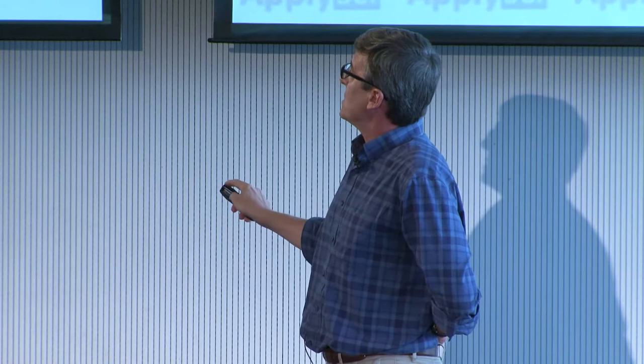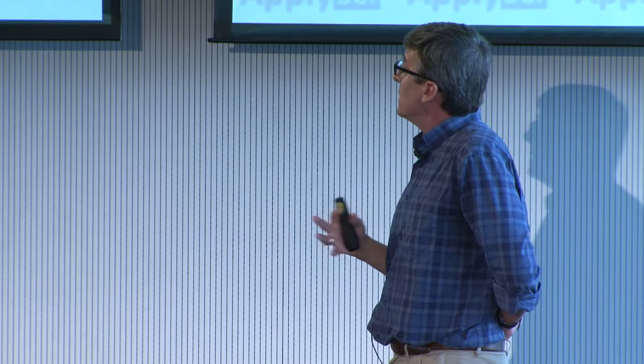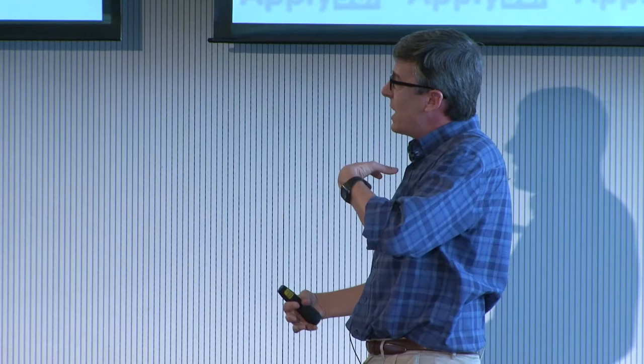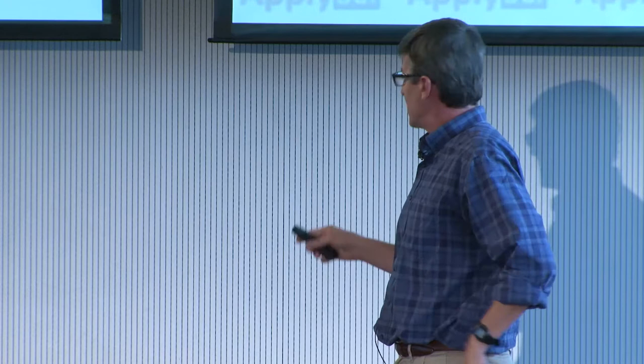So it has a pair of LEDs, one red, one IR, and they're flashing on and off out of sequence. There's a photo detector here that's measuring backscattered light. And from that kind of information, you can determine continuously the blood oxygenation level. You can also capture photoplethysmography in this way. So it turns out those two devices, one on the chest, one on the foot, allow you to reproduce full vital signs information at clinical grade quality, quantitatively corresponding to the old style hardware systems that I showed you before with the hardwired interfaces.